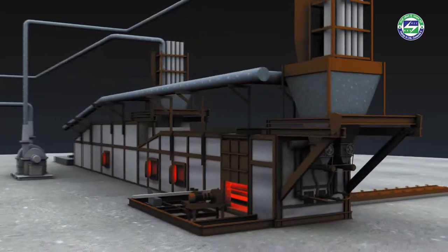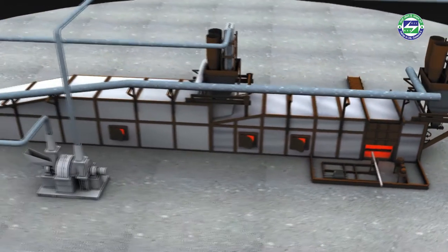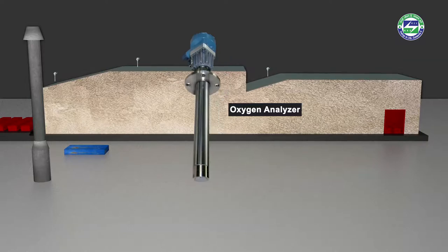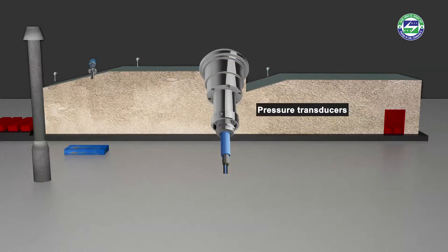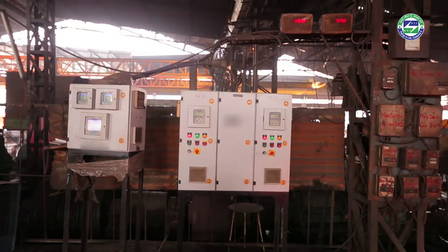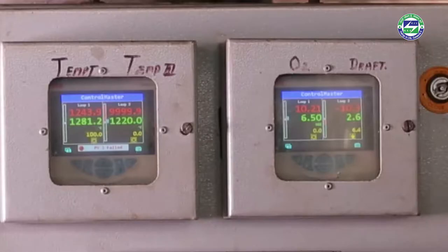A Level 3 PLC-based automation and control system consists of monitoring devices like thermocouples to monitor furnace temperature, a zirconium-based online analyzer for gauging oxygen percentage in the flue gas, and pressure transducers to monitor furnace pressure. The system also consists of a PLC panel to receive feedback from the sensors and control the furnace parameters.